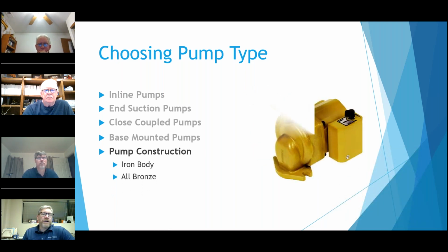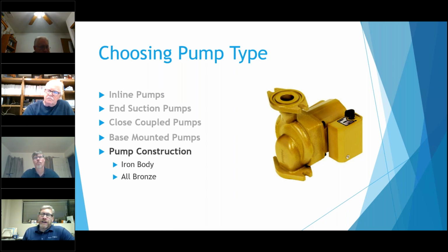Then you've got bronze, which is another material that we use. Those are almost exclusively used on hot water recirc loops. If you use a cast iron pump on a hot water recirc loop, eventually the inside of that is going to rust, and you get these little rust barrels. Think of when you see a boat sunk in the ocean, with all this little rust hanging off the railings of the boat. That happens inside of the pump, because that water is highly oxygenated, and it will start to attack the pump body if it's cast iron. Eventually, there will be enough rust inside that on these smaller pumps, it will lock them up to where they won't run.